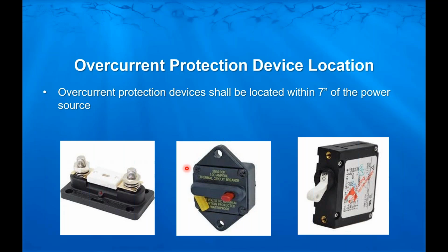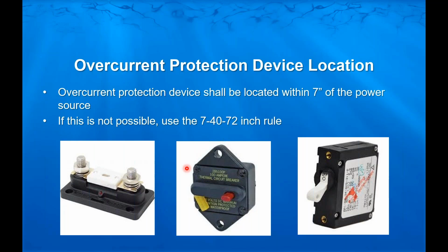Now, overcurrent protection devices for our wire that we just hopefully sized properly. Some examples of what they are, and the basic rule that our overcurrent protection devices need to be located within 7 inches of the power source. That applies to AC and DC. It's mostly a DC concern, and I'll bring up where it falls in AC most of the time, but it applies to both equally. If it's not physically or practically possible to get it within 7 inches, then we have what we refer to as the 7/40/72 inch rule, and really it's exceptions to the 7-inch rule.